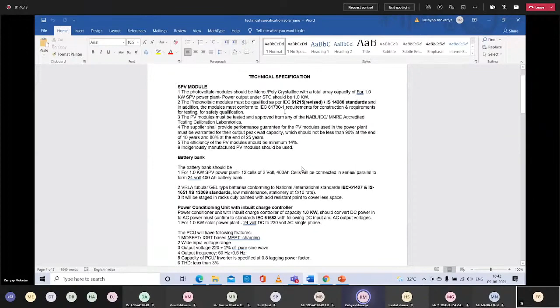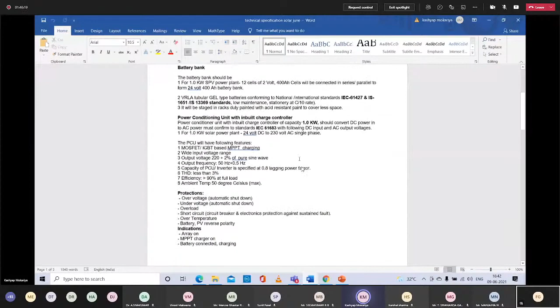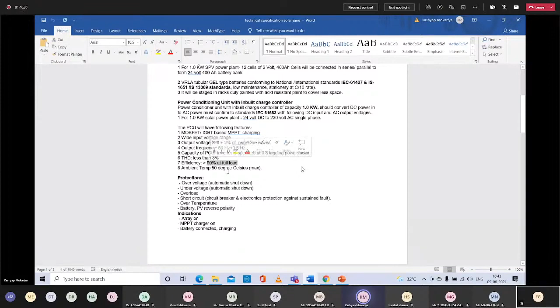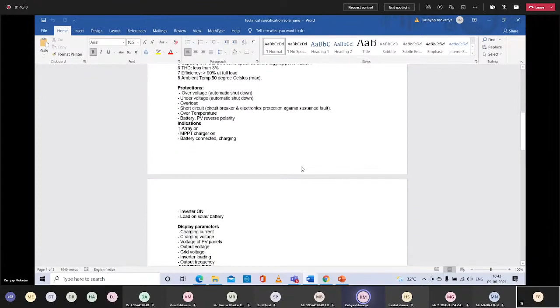So the standards, the efficiency, the guarantee, the controller, what type of controller I need, what THD expectation I have, I have to mention, because I cannot specify the same controller for a 10% THD and for a 3% THD. And obviously I have to mention the efficiency I am expecting at full load also. Protection: I have to mention over voltage, under voltage, overload. Now one thing I did: these are only a sample 5, but I gave them a list that these indications should be there when I receive my panel, and these display parameters should be there. It should be easily readable for me at that time.